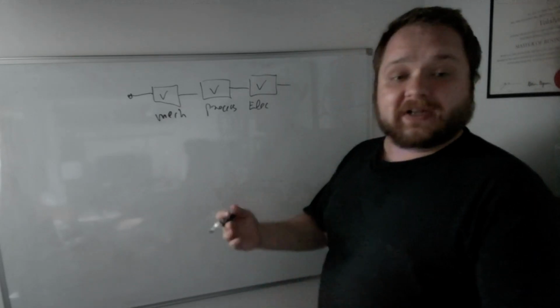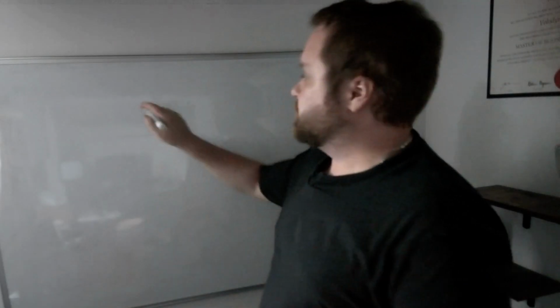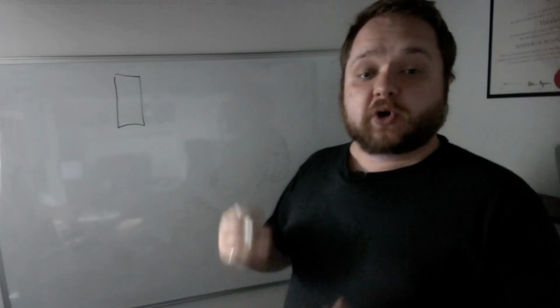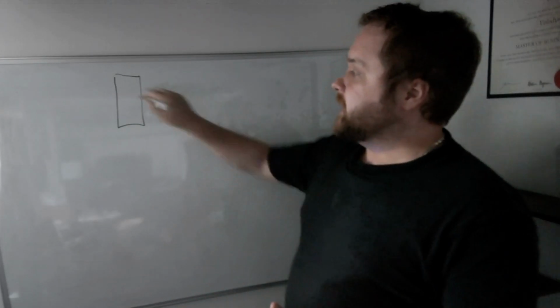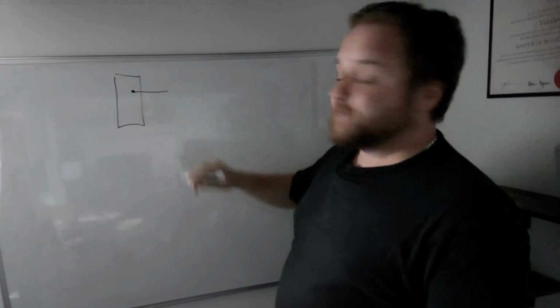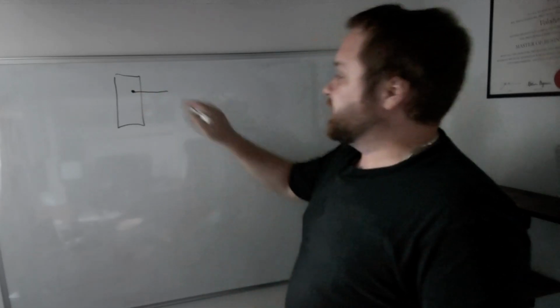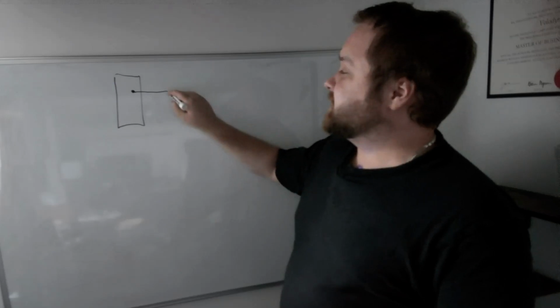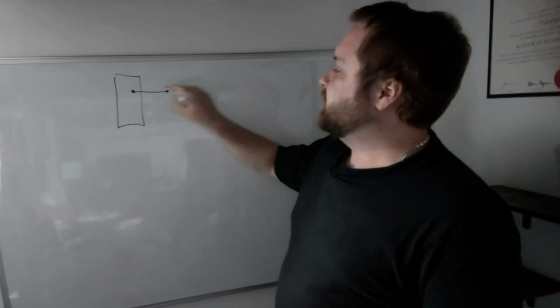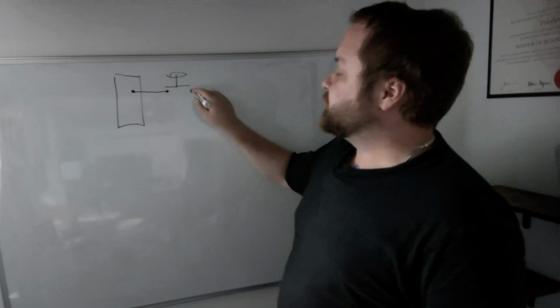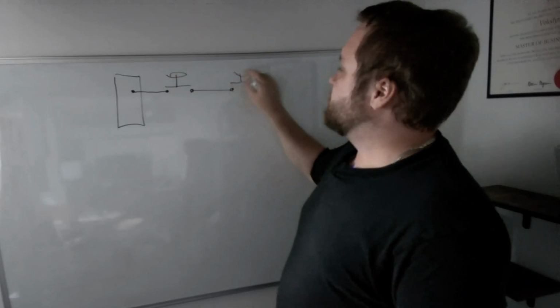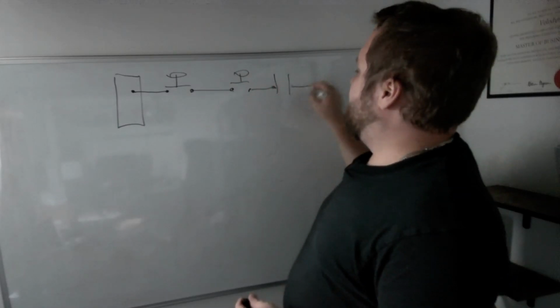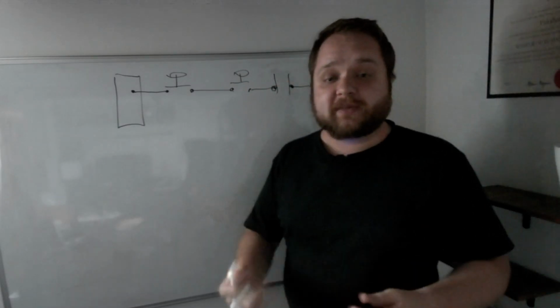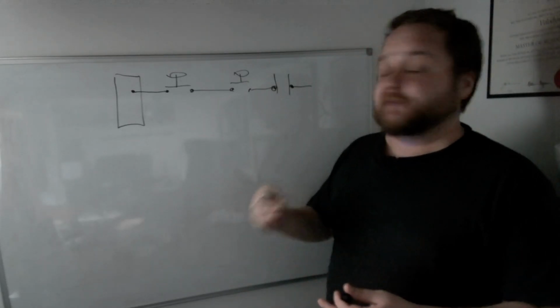So how do we do that with an electrical circuit? Let me just erase that really quick. What I will be explaining is the most fundamental basics of safety circuits. Normally, you will have what's called a safety relay. The safety relay is going to have a contact which, and bear with me, we'll get into dual channel safety, is going to check different devices. This can be represented differently depending on your drawings, but this is going to be an e-stop, this is going to be another e-stop, and this is going to be a light curtain. How it's represented really depends on the schematics, but that doesn't necessarily matter in the context of this specific visual.